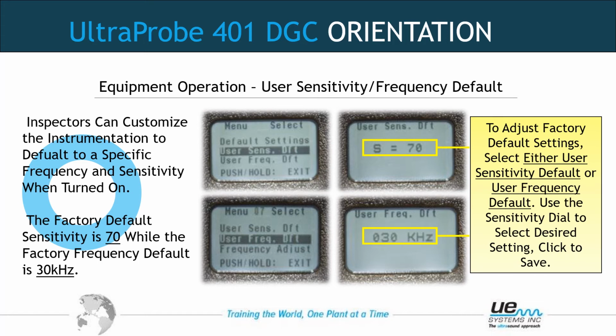Moving down the menu items, user frequency default. Again, where does the unit come on if no baseline information is available for it to read? 30 kilohertz is the default setting. If you choose to do extreme slow speed bearings and you want it to always come on at as low as the frequency will go, 20 kilohertz, you may choose 20 kilohertz here. That way it always defaults to 20 kilohertz. Again, it does not lock you from adjusting the frequency, just where does it come on, or if there's a blank spot for a reading with no baseline information.